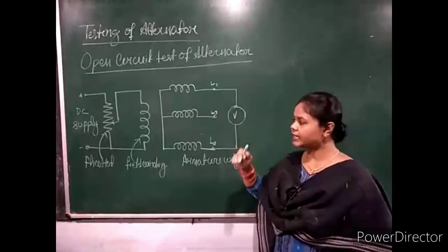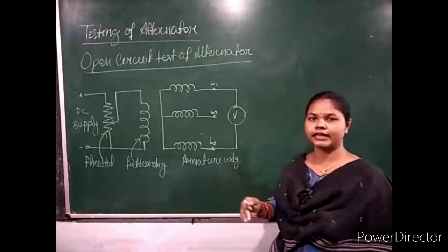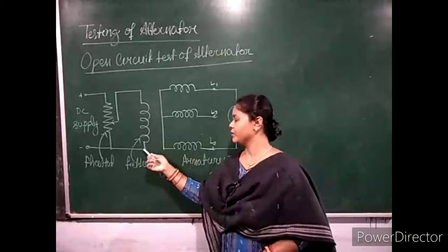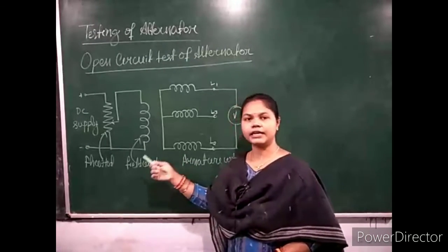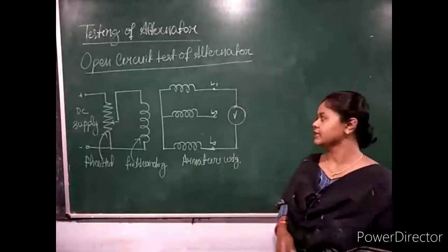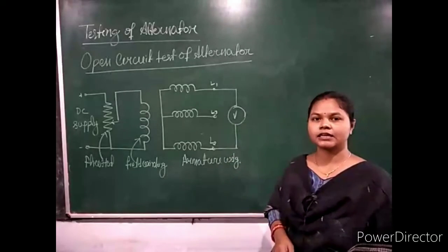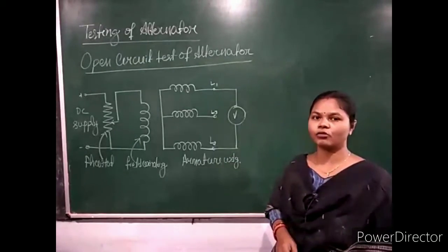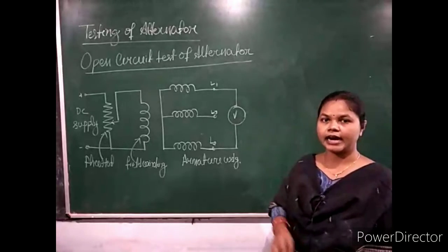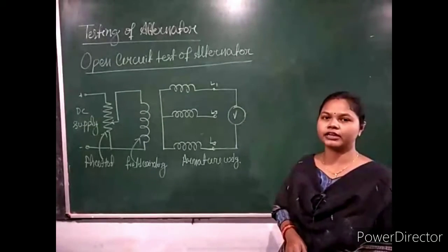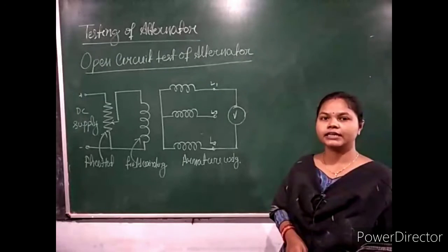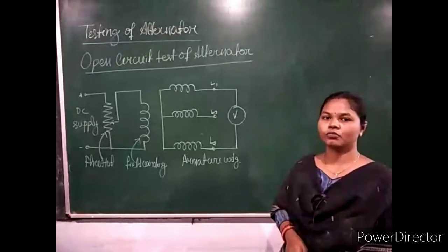Now, you increase the rheostat in such a way that, with the increase in field current up to some extent, the voltmeter gives just above the rated voltage of the alternator, and you have to note down that value, which is the open circuit voltage.